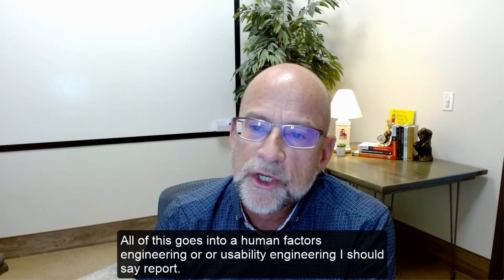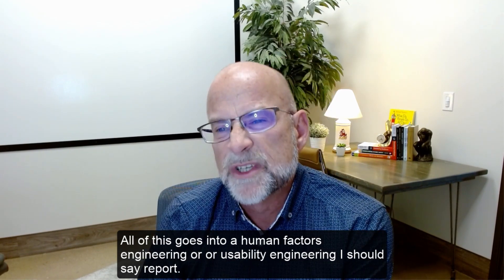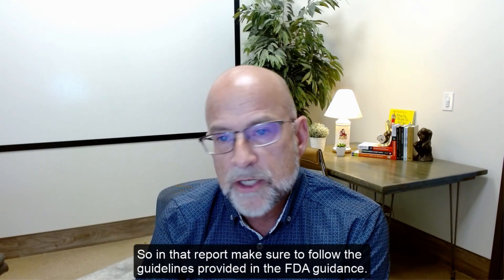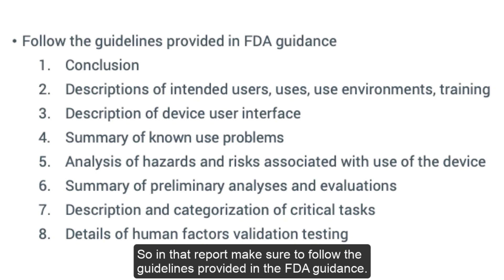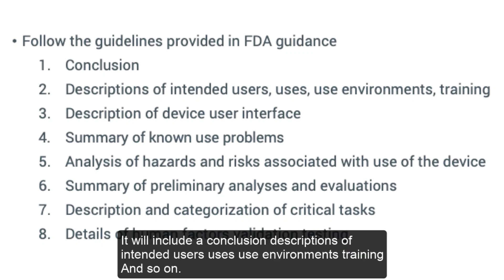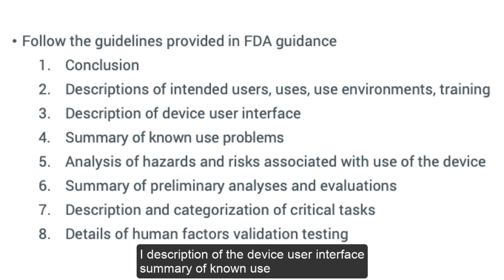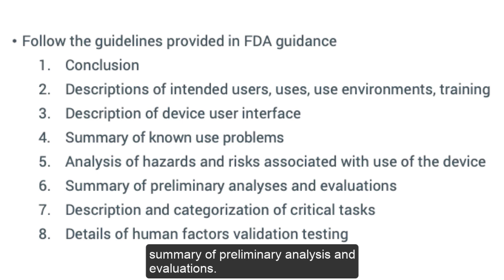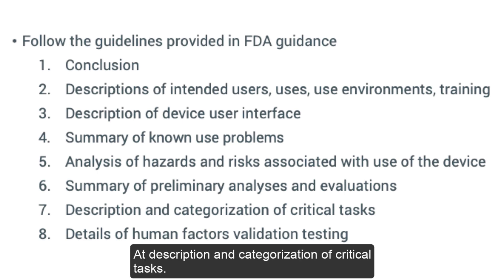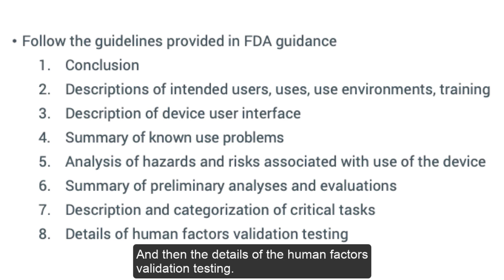All of this goes into a usability engineering report. Make sure to follow the guidelines provided in the FDA guidance. The report will include: a conclusion, descriptions of intended users, uses, use environments, training; a description of the device user interface; a summary of known use problems; an analysis of hazards and risks; a summary of preliminary analyses and evaluations; a description and categorization of critical tasks; and the details of the human factors validation testing.